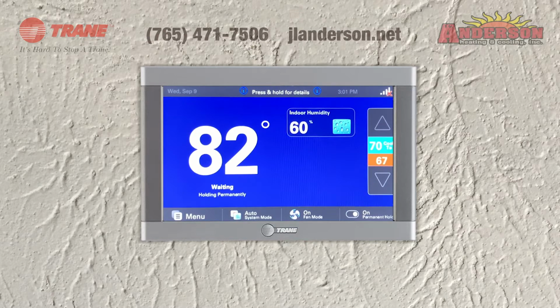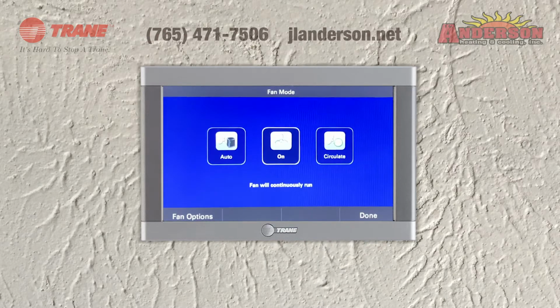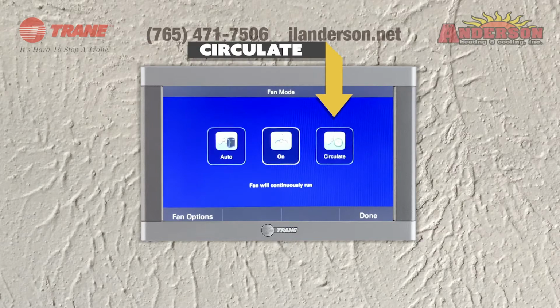I'm going to hit the fan button now. There are 3 different options. The auto button means that it's only going to run the fan when it's heating or cooling. The on button means that it's going to run the fan all the time, including when it's not heating or cooling. The circulate button is kind of halfway between on and auto. It's going to let you choose how many minutes out of every hour you want the fan to run if it's not heating or cooling.